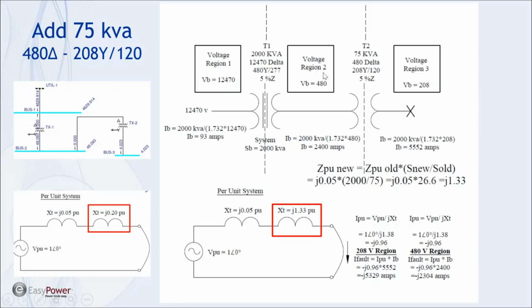The other area that I try to emphasize too is when we get into control transformers, and again, when you get into a control cabinet, you don't know whether you're going to be supplied by a DC supply or a control transformer, or you can have control voltage, believe it or not, on a 208Y120 system. We can have control voltage coming off of one of the phases of our supply transformer, whether it was a 75 kVA, or if we go back up above to one of our, like, a 1,000 kVA 208Y.